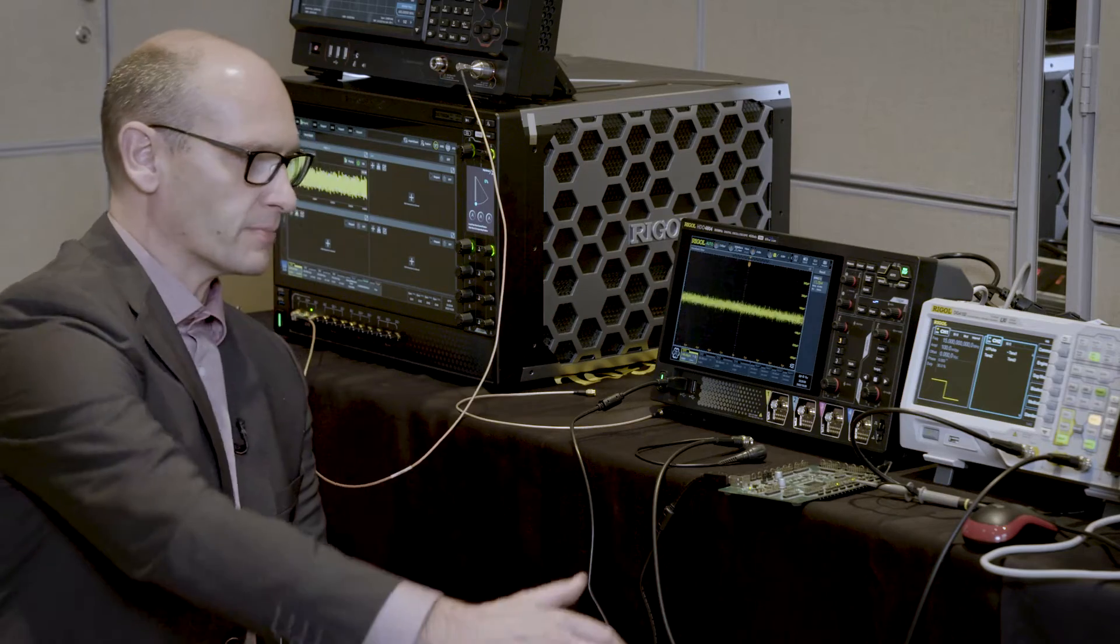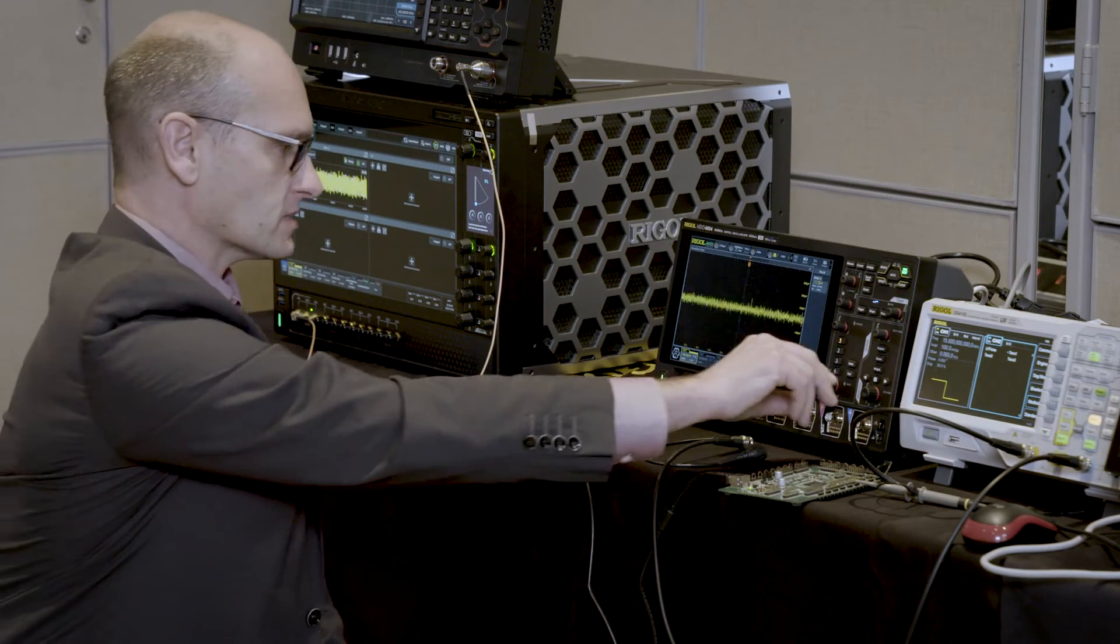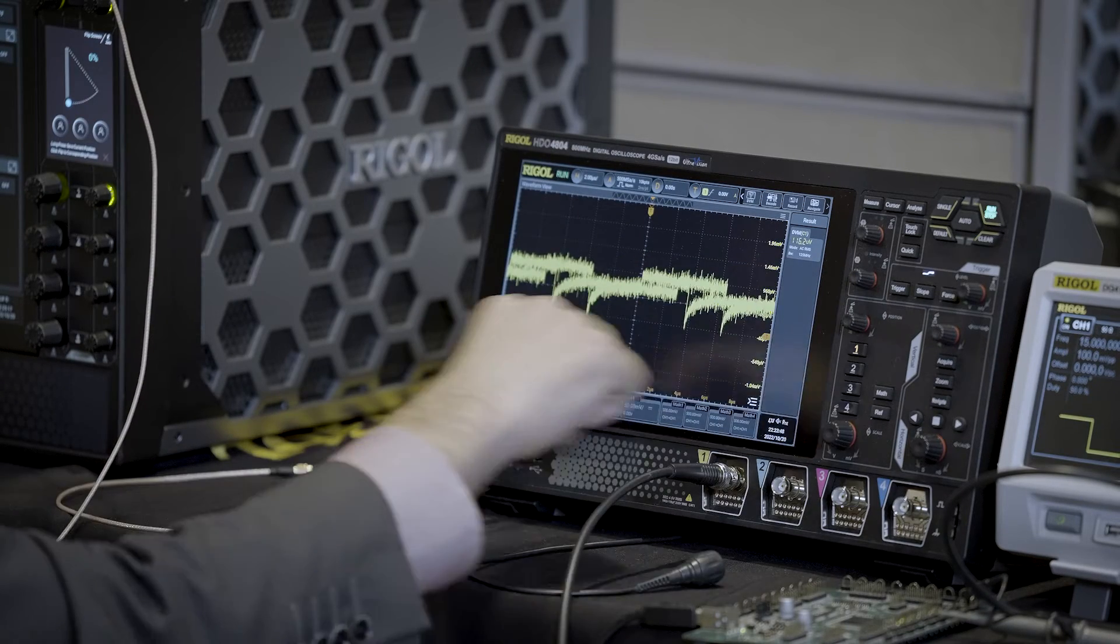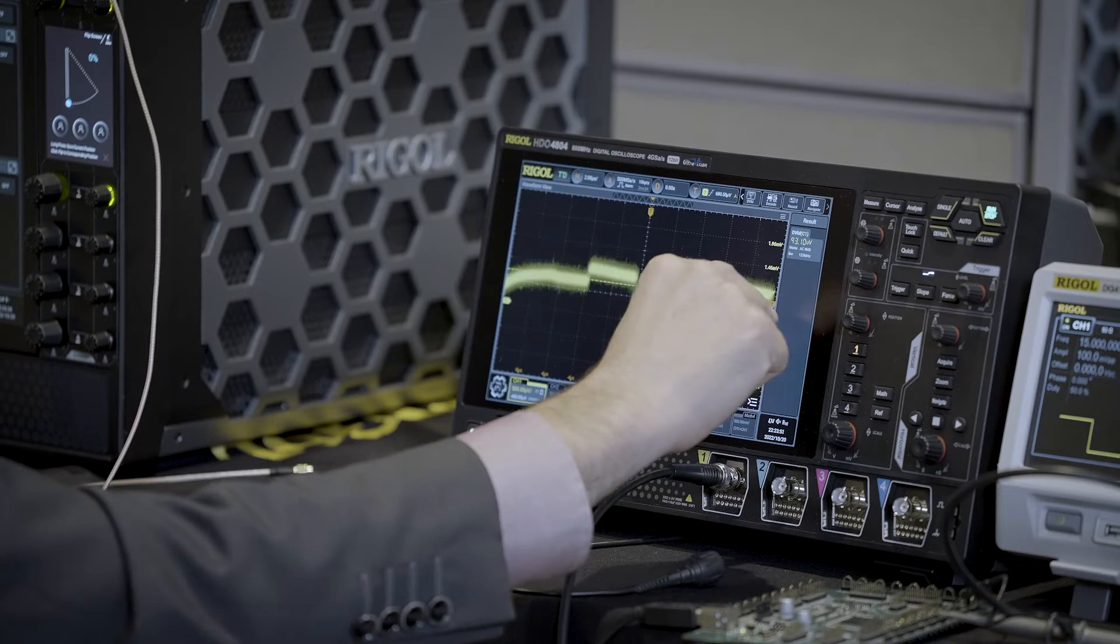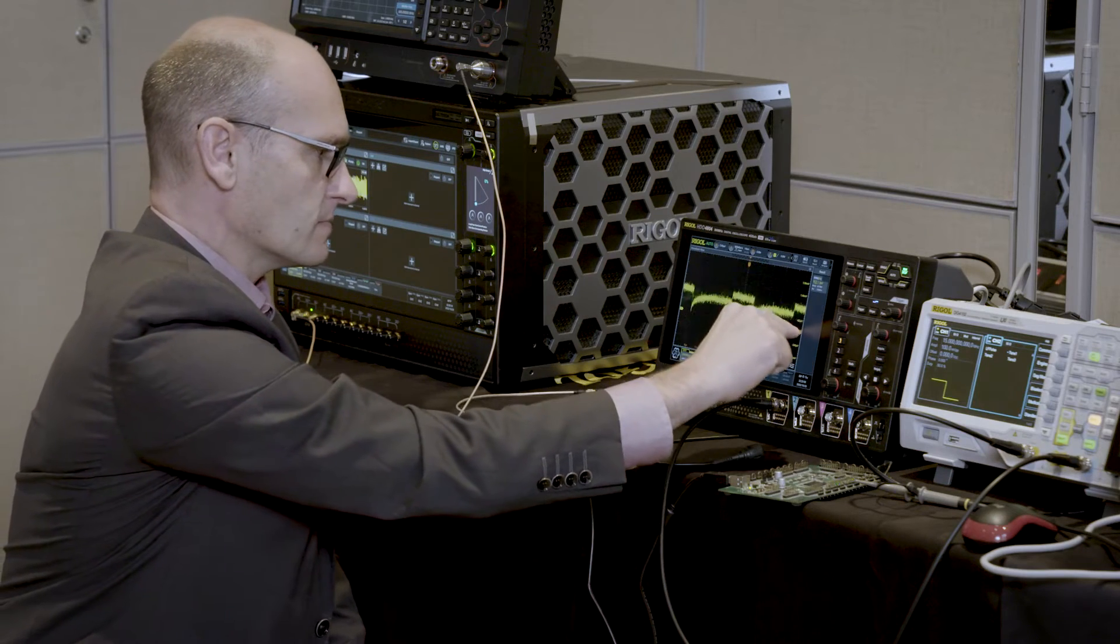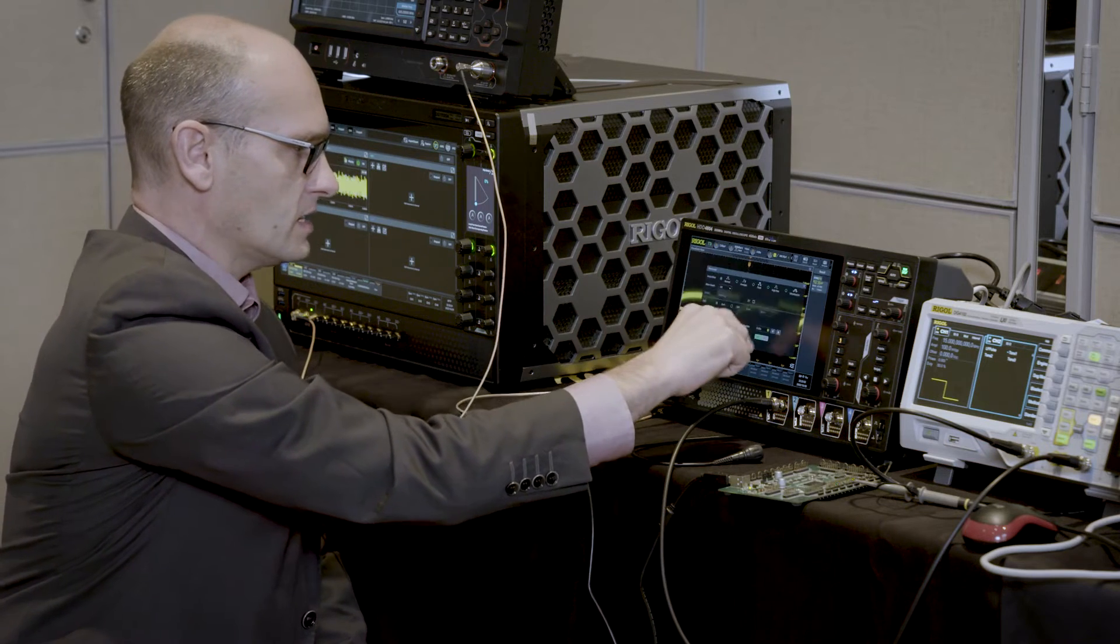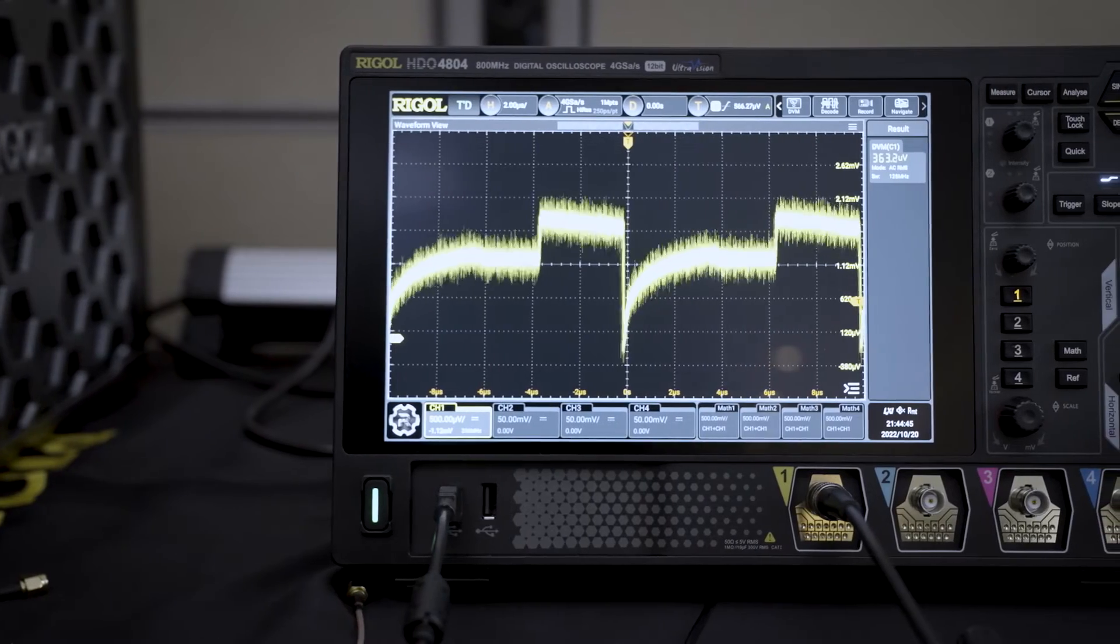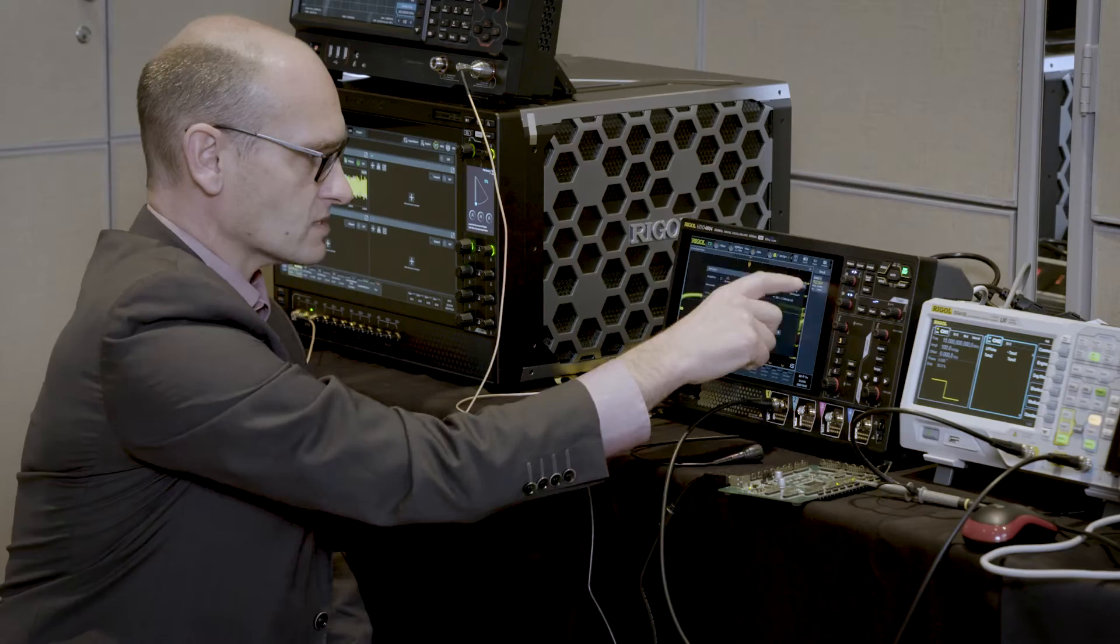With that noise level behavior and with the 12-bit, we have a chance to measure quite small signals. For example, I generate a very small ARB signal with that adjustment and connect this to the scope, and you can see that we can even with these very small settings see the signal on the scope. Even with high resolution settings we have the chance to select high resolution with 16 or 14 bits to make the trace even in these very small settings quite clear.